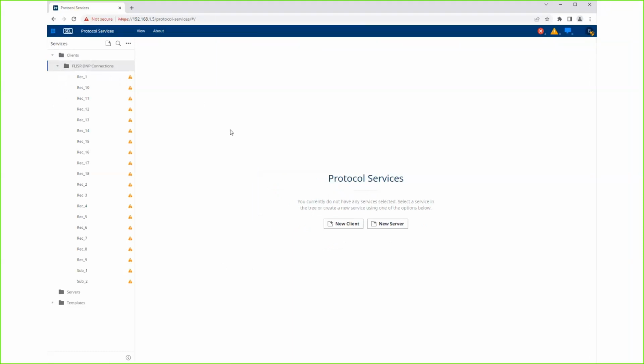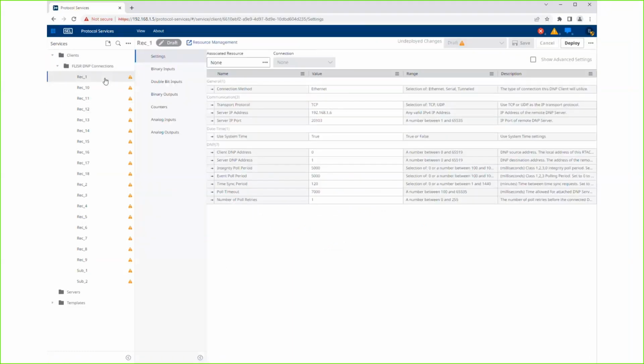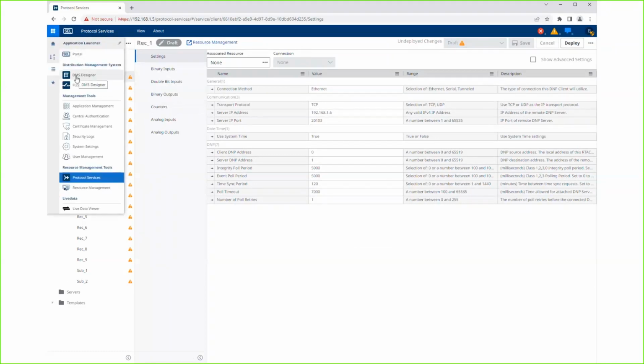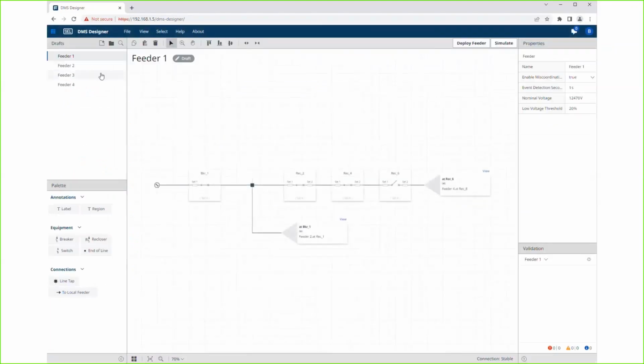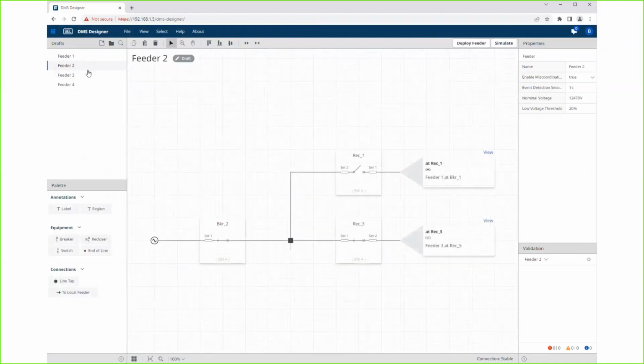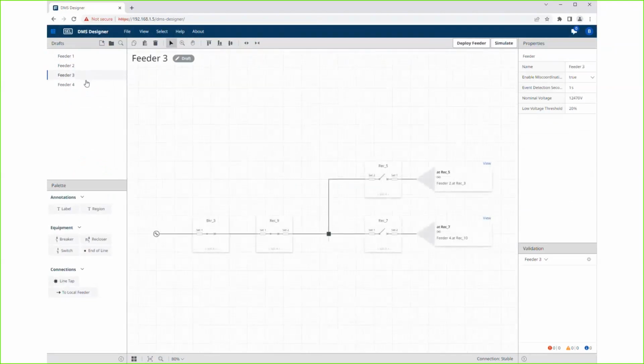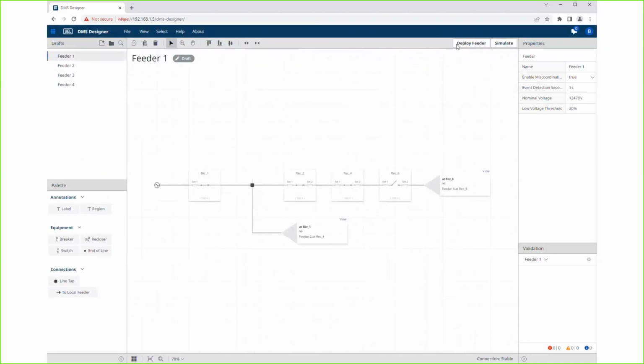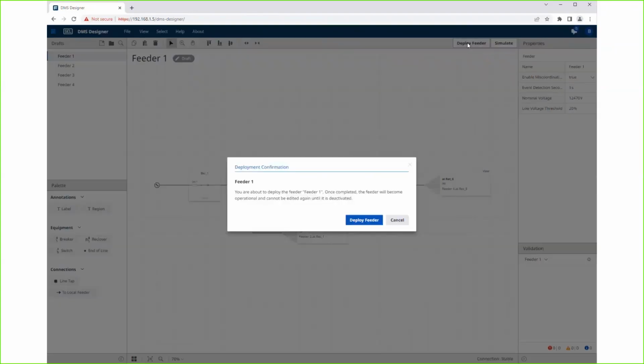There we go. So we have all these reclosers and 2 substation connections, 2 RTU connections. So you can see their IP address settings, the right server IP port, everything is set up correctly. All my data is here. And if I go back to DMS Designer now, you will see that all of the errors are gone. And look at that deploy feeder button. It is now clickable. It's not grayed out and disabled anymore. So every single feeder looks to be happy. There's nothing in the validation window, 0 errors, 0 warnings, 0 info, and I can deploy this feeder.